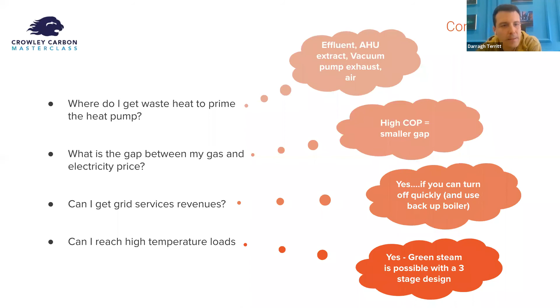This next slide is a configuration we're currently working on with a number of our customers. It excludes some details as they are live projects, but it's a 3-stage heat pump, each stage with a different technology and a different refrigeration gas. First stage lifts temperatures from circa 30 to 65 degrees. Second stage, from 65 to 105, water or atmospheric steam in a reboiler arrangement possibly, and then to 2-bar steam in the final stage. A lot of sites have existing steam infrastructure in place, and there would be a huge expense in removing that and replacing it with hot water. So that's where green steam can really play a relevant role, powered by green electricity.